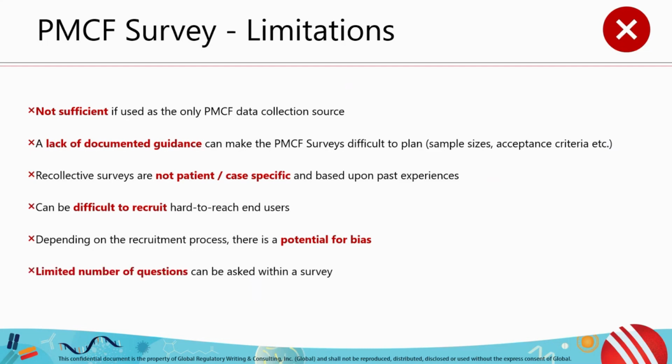With a survey, I would recommend it being as concise as possible. Don't make it overly burdensome for respondents, and that means you do have a limited number of questions you can ask. And with everything with PMCF, what this means is that manufacturers are collecting more data. Also, because there's lots of safety data, you're potentially collecting adverse events and complications. So this increased data collection is a resulting burden on your complaint handling teams. Make sure they're aware of this before you go down the route of PMCF surveys or PMCF data collection.